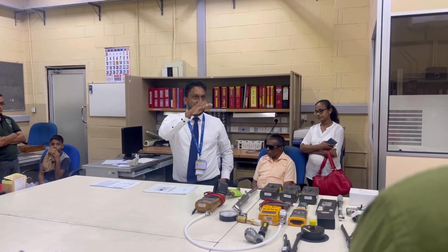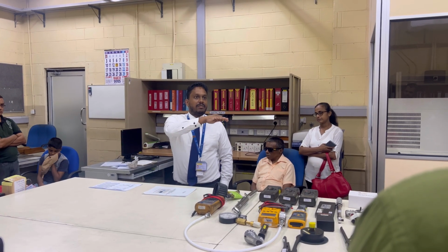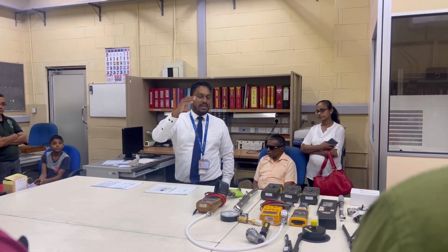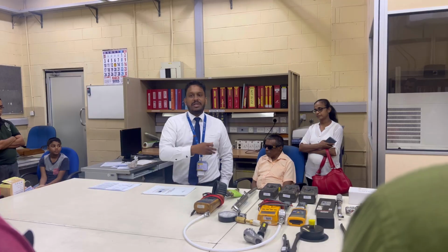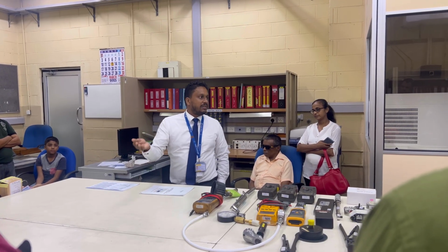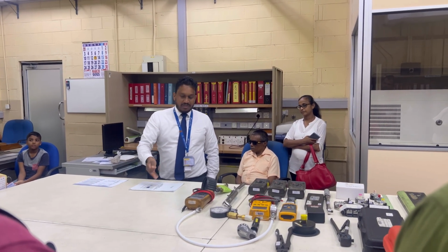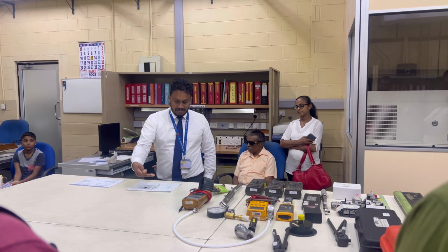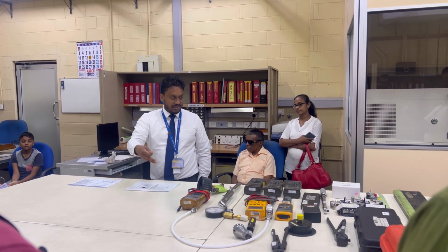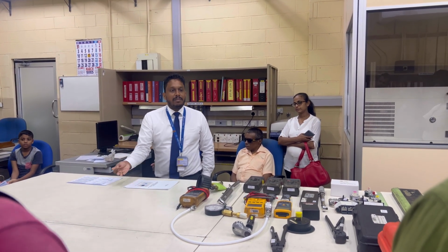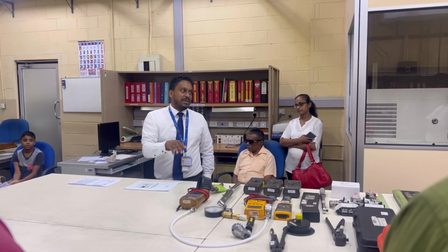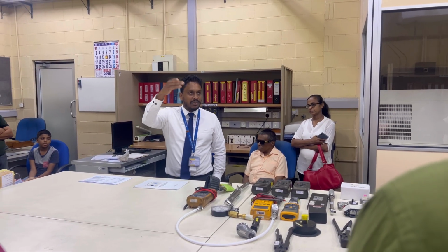So what we do, we have a temperature variation of about 1 degree. Then we check for 1 degree how much expansion can occur in both these instruments, the test piece and the measuring rule. Then we put that into the uncertainty, in simple terms. So like that we see what the other parameters are.